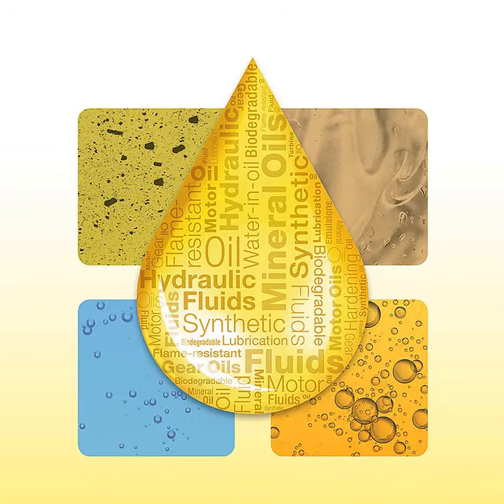Now let's move to another stage that often surprises people: filling the system with new oil. Here's something many people don't expect. Just because oil is new doesn't automatically mean that it's clean enough for use in a hydraulic system. In fact, brand new industrial lubricants are often dirtier than the cleanliness levels required by hydraulic and lubrication systems. It's easy to assume that fresh oil can simply be poured straight into the reservoir. But doing that can undo all the effort spent cleaning and assembling the system. That's why filtering new oil before it enters the machine is so important.